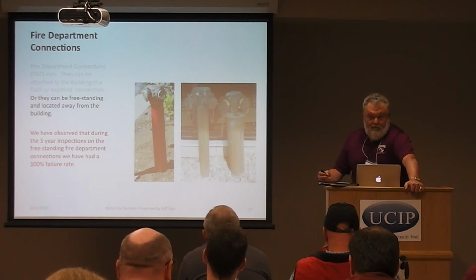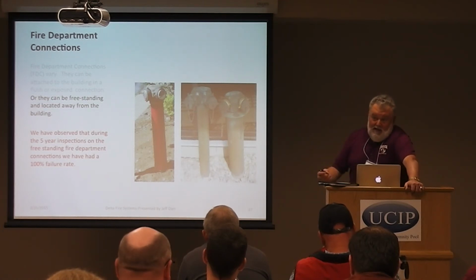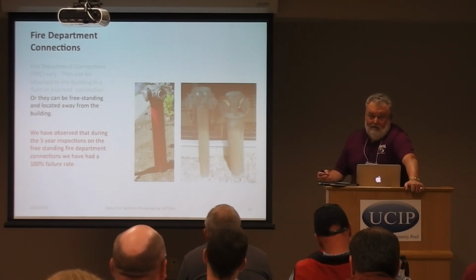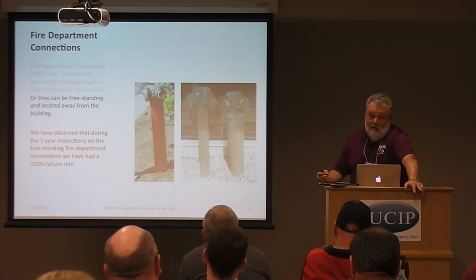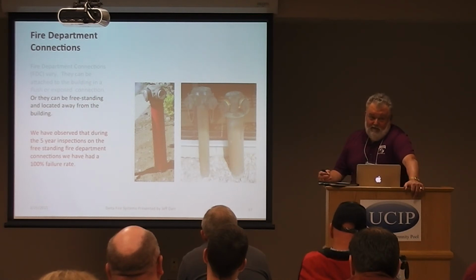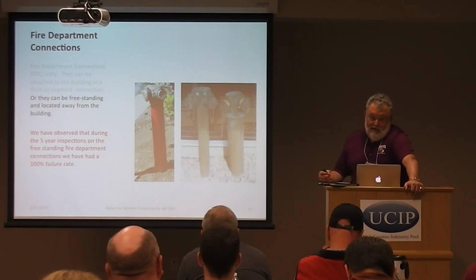One interesting note on the freestanding fire department connections, Ken has kept a careful eye whenever we do a 5-year test on these, because every 5 years we want to actually put water through these. We've had 100% failure rate on freestanding fire department connections. So my concern is you have a firefighter that now has a false sense of security that he's going to be able to pump into that, and that system's not going to work for him. So I recommend that you have wall-mounted fire department connections.